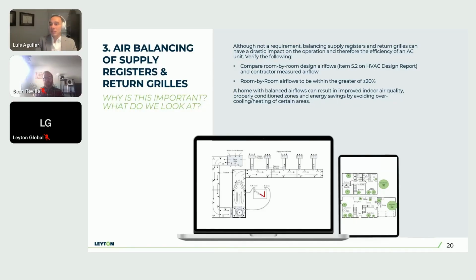Okay, so air balancing. So another common issue. So if we have sufficient airflow, if the unit is operating, we have a correct pressure difference in the refrigerant, and then we have sufficient airflow, there still may be an additional issue that we run into, and that's when you have unbalanced supply registers and return grills. So this is a very common issue as well. While I would like to note that this is not a requirement, but it's very much beneficial and recommended as well by Energy Star. So we want to make sure that the airflow for each zone throughout the home is being met. So just like there's a system design, a total CFM or a total cubic feet per minute for the unit, we want to ensure that the CFM per zone is being met. So we take a look at the design report, which will list every single zone in the home, and it'll have a required CFM that has to be met.